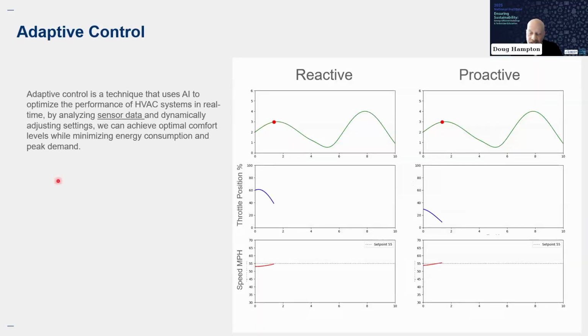Adaptive control is a technique that uses AI to optimize the performance of HVAC systems in real time, again by analyzing sensor data. It's all about the sensor data - how accurate are the sensors? If I'm trying to control a 20,000 CFM air handler with a $5 discharge air sensor, it's probably not going to be as accurate as I would like it to be.